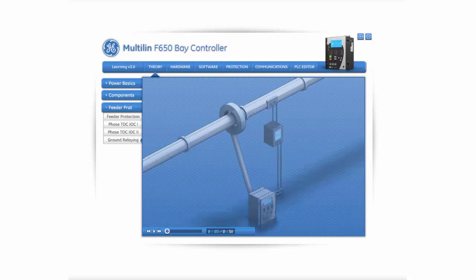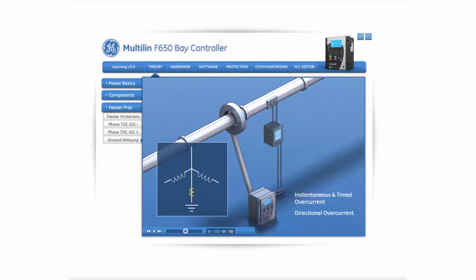Ground relaying of sub-transmission and distribution circuits is accomplished by means of instantaneous, time-overcurrent, and directional overcurrent elements. These elements can generally be made to operate faster and with more sensitivity for ground faults, and still maintain selectivity because their connections render them immune to load currents. The directional element requires a source of polarization that is obtained either from a current transformer in the neutral of a power or grounding transformer, or from the broken delta of a grounded neutral Y-delta potential transformer bank.